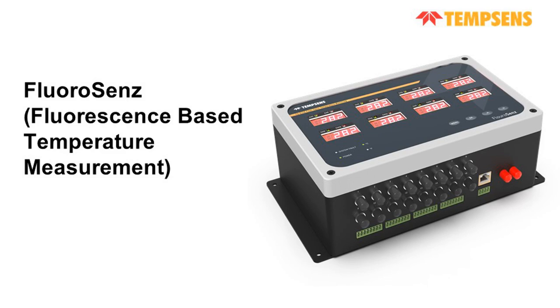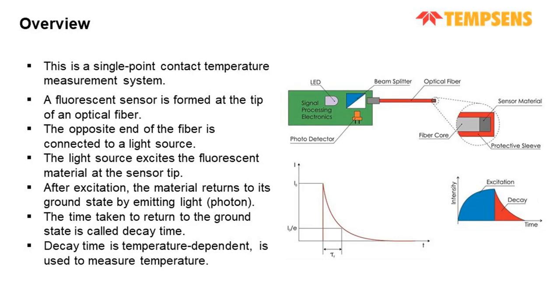It is based on fluorescence material time decay principle. So this system represents a single point contact temperature measurement technique. So it can measure a single point with a single sensor. And at the core of the sensor, there is a fluorescent material which is embedded at the tip of an optical fiber. And the other end of the fiber is connected to a light source, which is used to excite the fluorescent material. When excited, the material naturally seeks to return to its ground state. And in doing so, it emits a photon, or a particle of light, we can say.